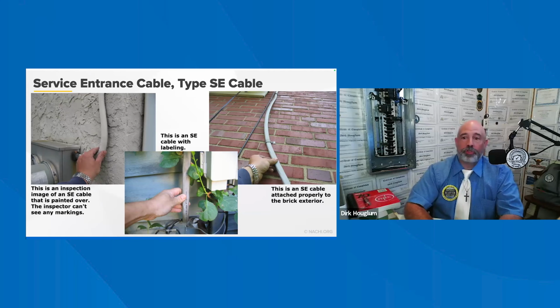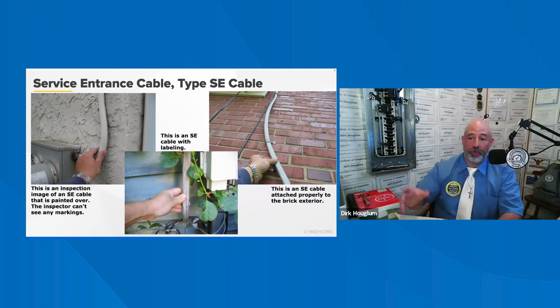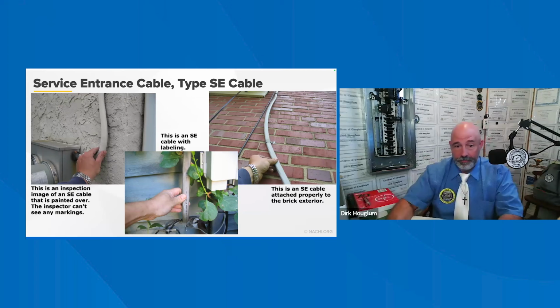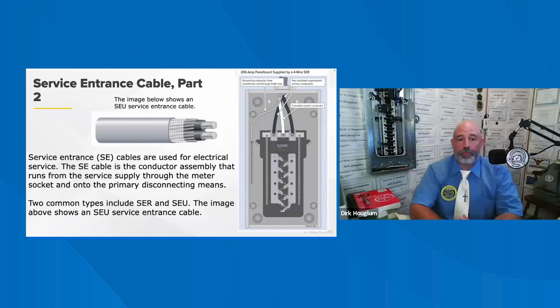At the top, it should have a gooseneck or a service head cap to keep the water out. If the gooseneck is used, the end of the cable where the wires come out should be sealed with a heat shrink sleeve to prevent moisture from getting in. The cable should also be secured, fastened to the building every 30 inches and within a foot of the top of the meter. That was good to know.